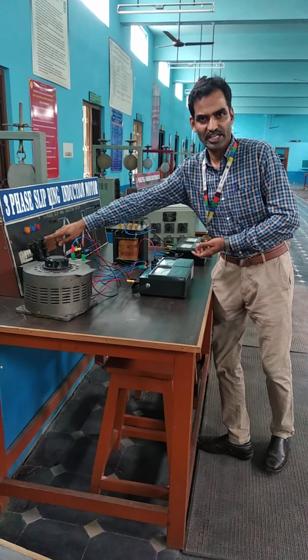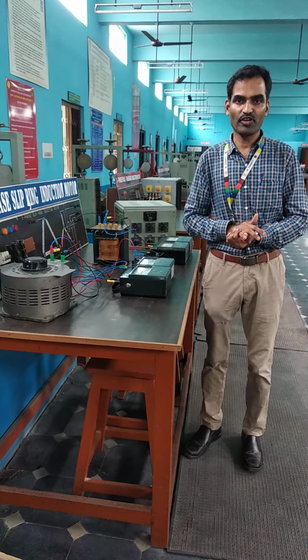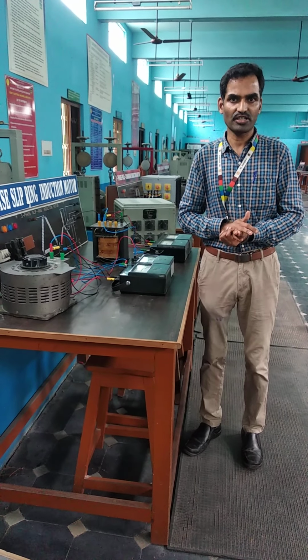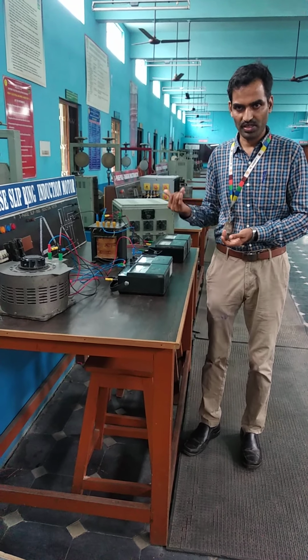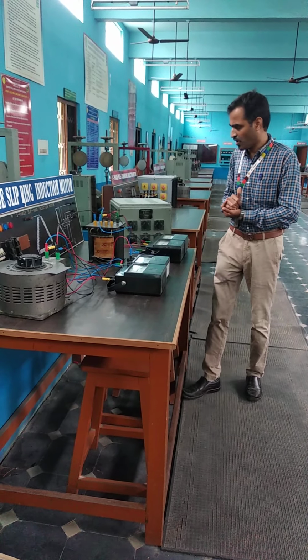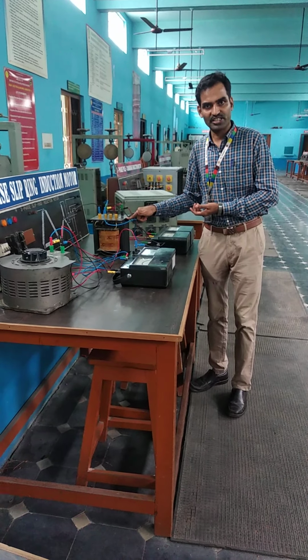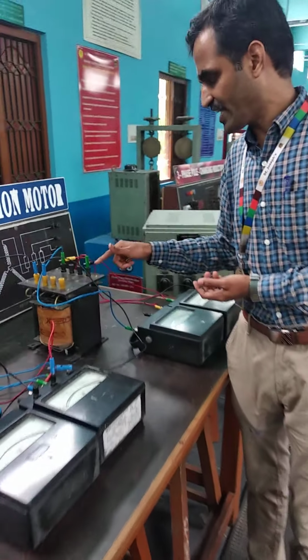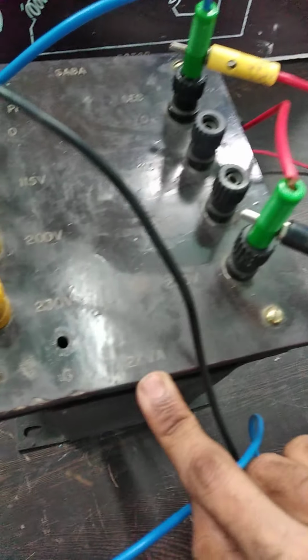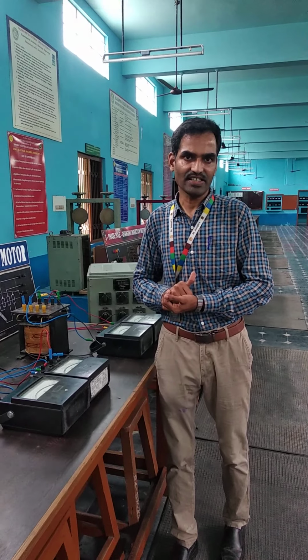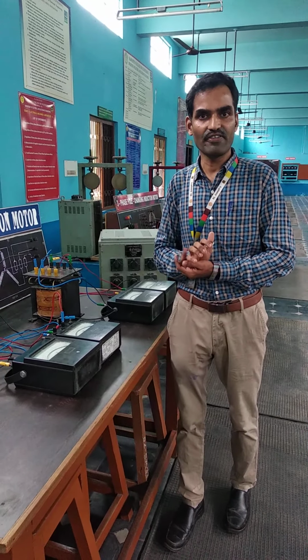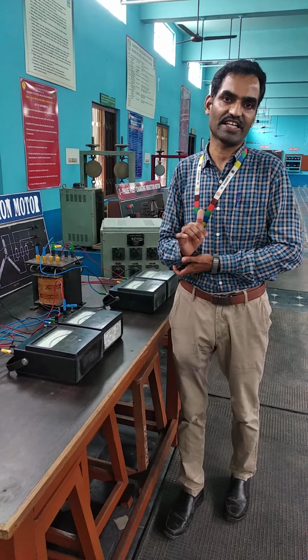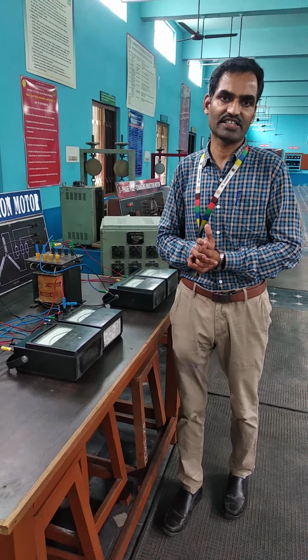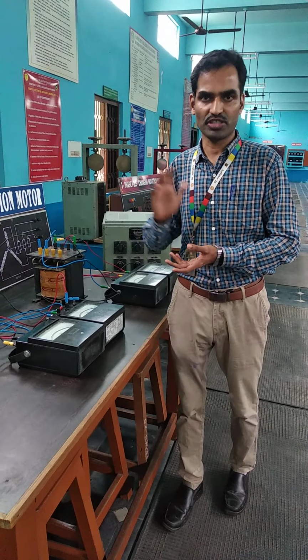Then we have to calculate the fuse rating. Since this is a load test, the fuse rating is calculated as 120% of the rated current of your transformer. For finding the rated current, the rating of the transformer is given as 2 kVA and the secondary voltage is 230 volt. With this voltage and power, I have to calculate the current, that is the rated current of your transformer. 2 kVA divided by 230 will give you around 8.69 amps. From this rated current, you have to calculate the 120% rated current, which is your fuse rating.